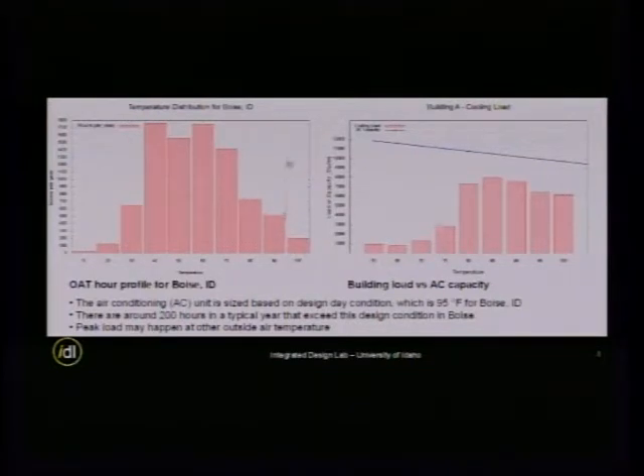So it's right here. Now, to make it even more complicated, this is one of the buildings that I simulated for this project. This is the cooling load, and I plotted it against the outside air temperature. And you can see here that the peak actually happened not at the maximum temperature, but somewhere when the outside temperature is at 85. So it's about 10 degrees less than the design day.